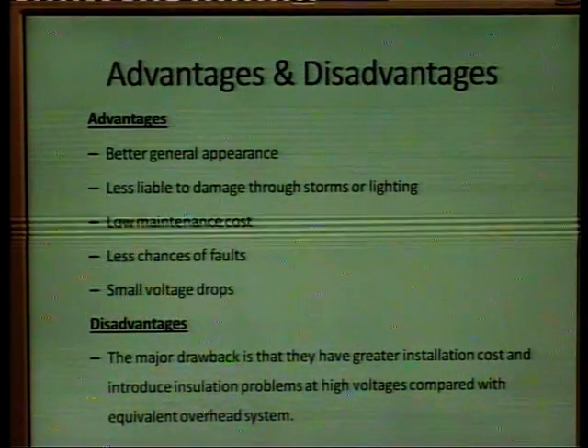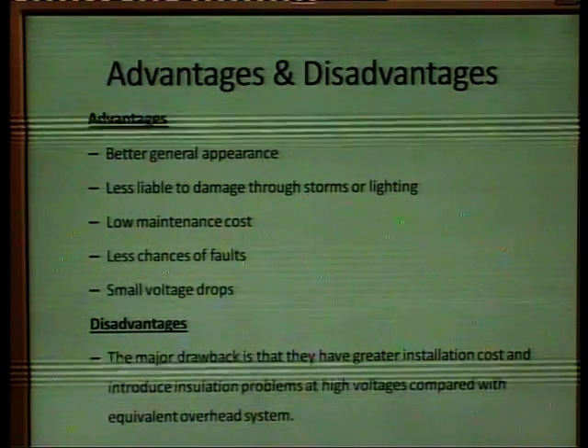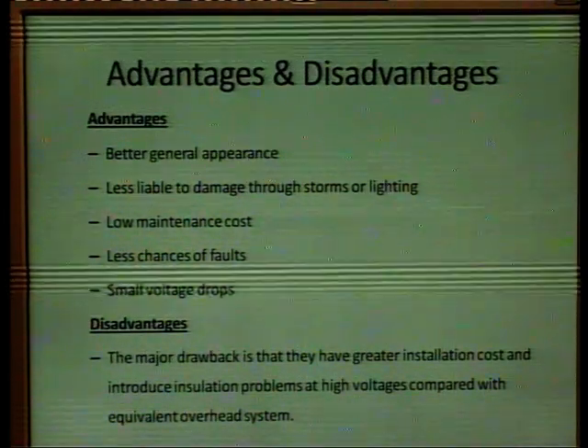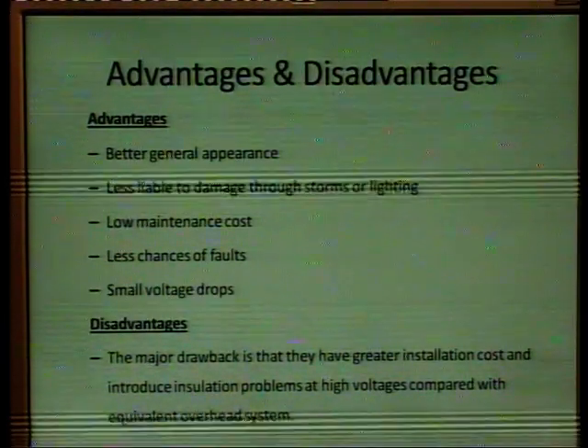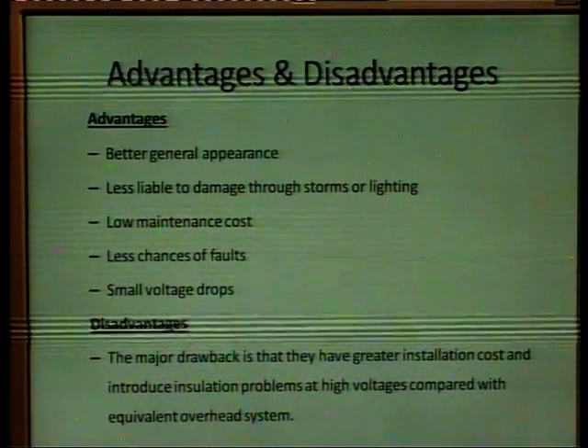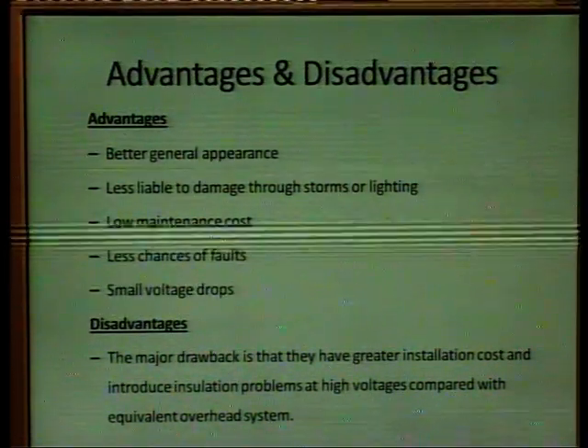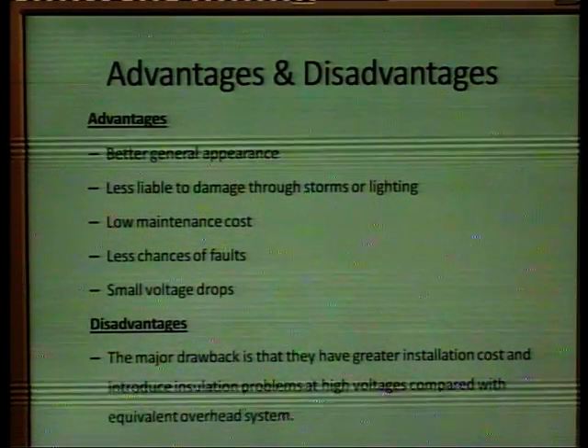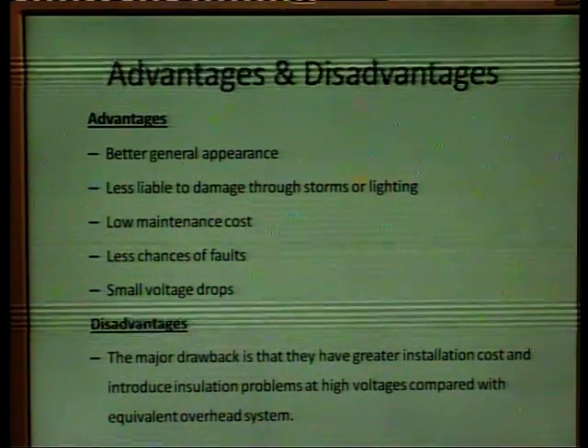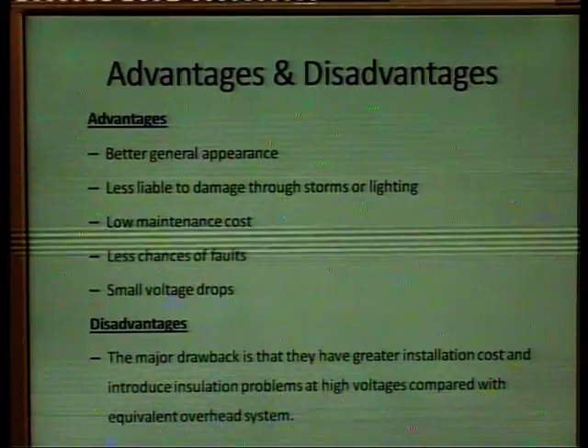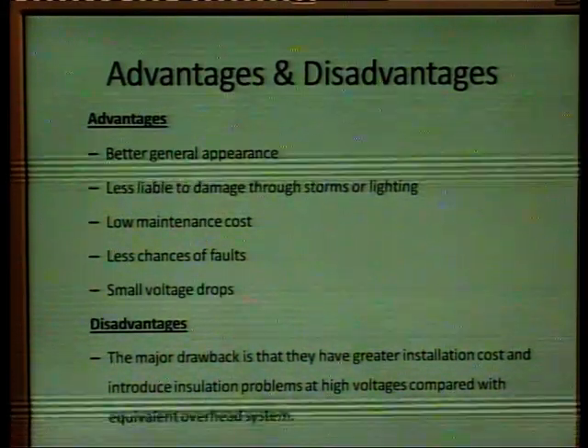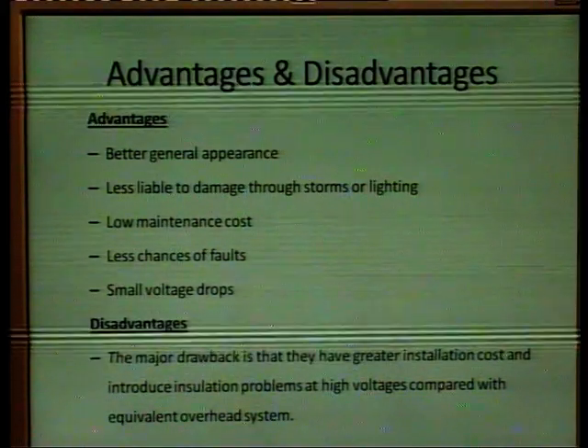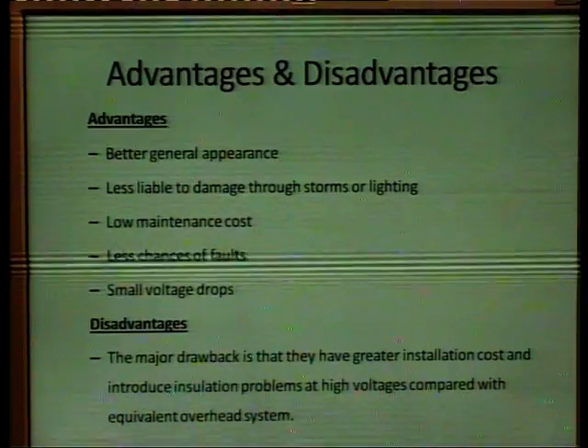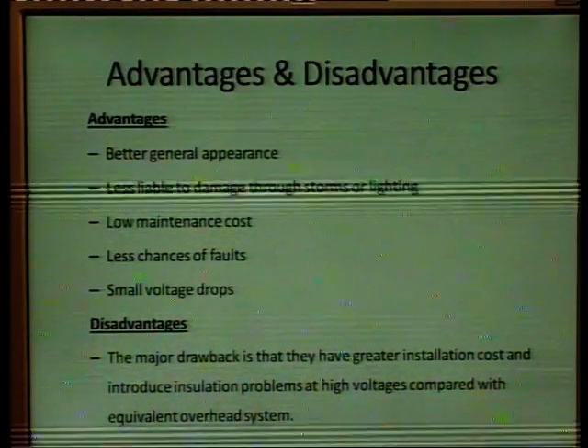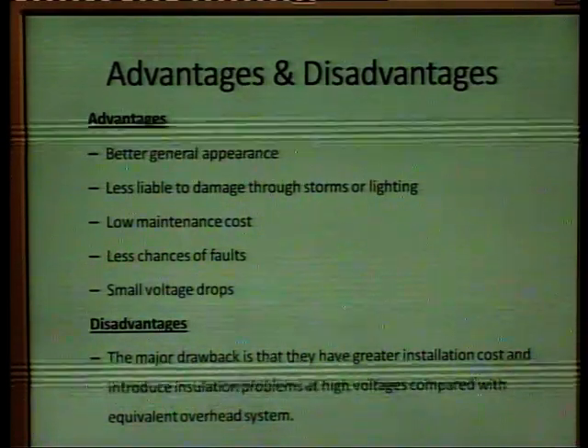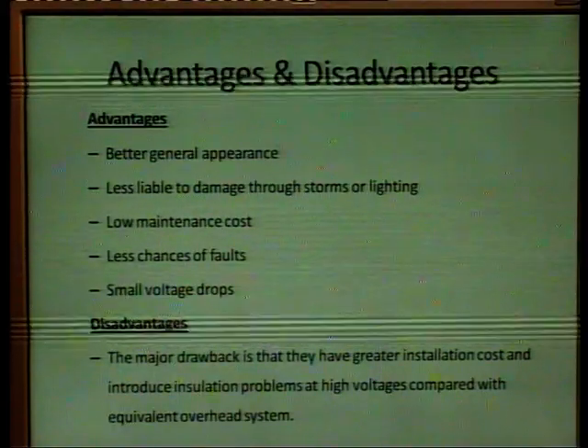So now we will find out the advantages and disadvantages of underground cables. Advantages: the first is better general appearance, as we don't need poles and shabby looks are not there. The second advantage is that it is less liable to damage through storms or lightning. As we know, whenever there are storms or thunder lightning, the overhead lines may be damaged due to disturbance by trees or by the wind. In underground cables, there should be no damage during storms or lightning.